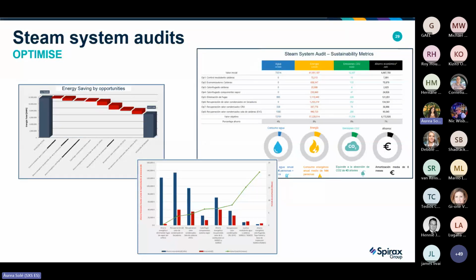That's just a screenshot of the report of one steam system energy audit that we conducted, where we can see that we start from the base case scenario, so how the steam system works for our customers and what the energy consumption is. We provide a set of optimization solutions, suggestions, basically. And if all of them are applied, we would get to a future baseload energy consumption. We also compare that with the return on investment of these optimization solutions, as well as the sustainability impact that each of these solutions can generate.